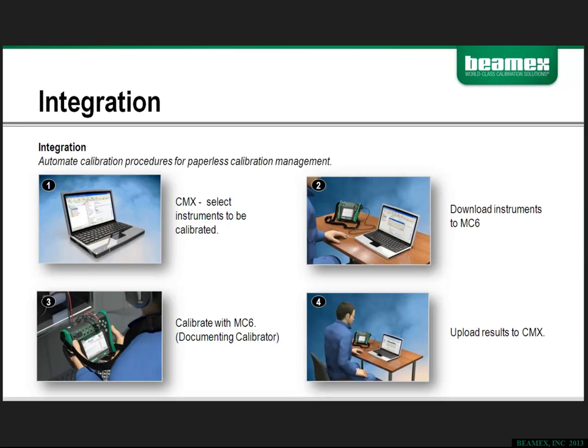But it helps you identify which instruments are due for calibration. And once you've identified an instrument or selected instruments that, say, you want to do for a particular shift, what you would do is select those instruments in CMX, and then in slide 2, you would actually connect your documenting calibrator, which what you're looking at there is the MC6, and you would basically drag and drop the information for those particular instruments that need to be calibrated directly into the MC6.